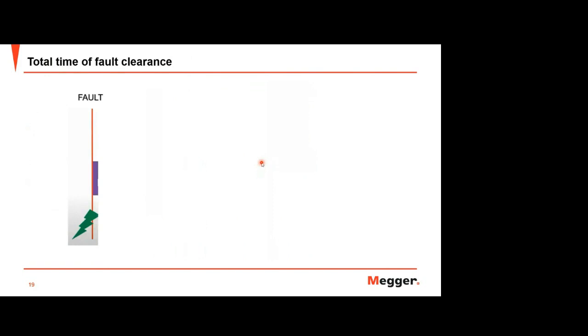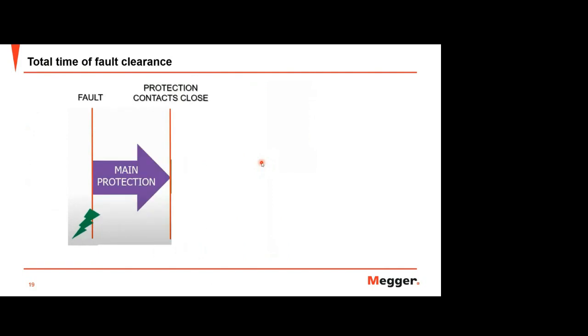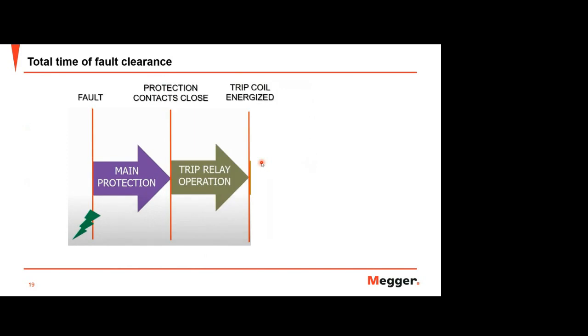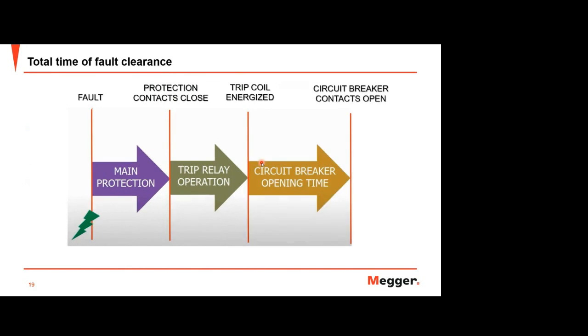This is the total fault clearance illustration. Actually, after the fault, the main protection will operate, and the protection contact on your relay will close. This will initiate the trip relay, which will energize the tripping coil. The circuit breaker contact will then open, and the fault will be cleared. In a high voltage system, some customers expect a range of around 30 to 50 milliseconds. The contact itself in the relay is mostly less than or around 8 milliseconds. And for the circuit breaker opening time from the first trip, some customers decide the maximum is 50 milliseconds. So in total, if you calculate, it is around 88 milliseconds.